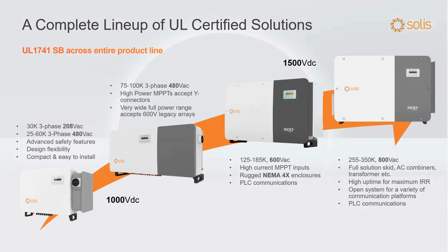480 volt AC is a very popular product here in the United States, as it's the main connection voltage, whereas 600 volts is common in Canada. Our 125 and 185 inverters are really appropriate for quick install without a secondary transformer, which is cost effective, and we're seeing a lot of folks utilize these inverters, which are rated down to minus 30C but can be used across much of Canada. The allowance of 1500 volts on rooftops in Canada also makes this product popular, with native AFCI and easy hookup, and the ability to set it up where the combiner box might be, since it's got essentially the combiner box right on the bottom of the inverter, or set it up in a central location. I want to show you a little bit about how we can enable that.